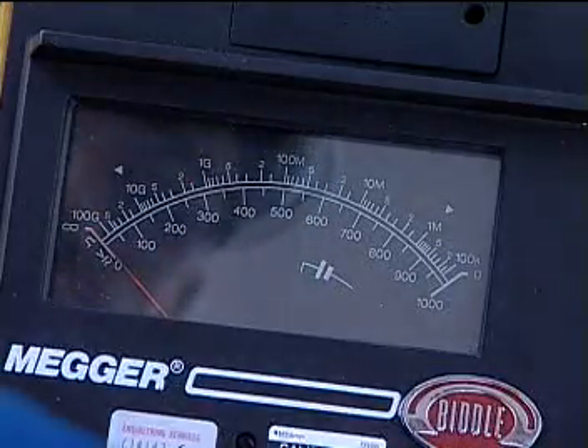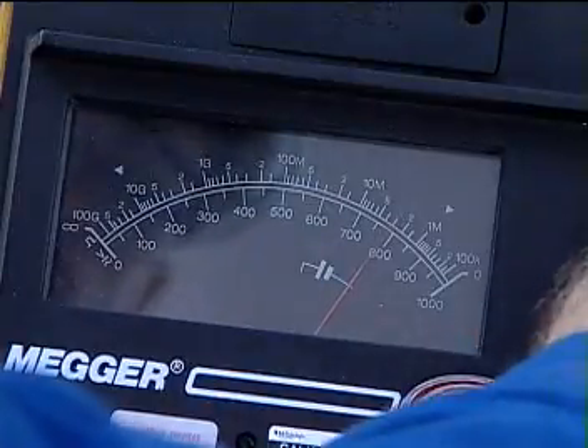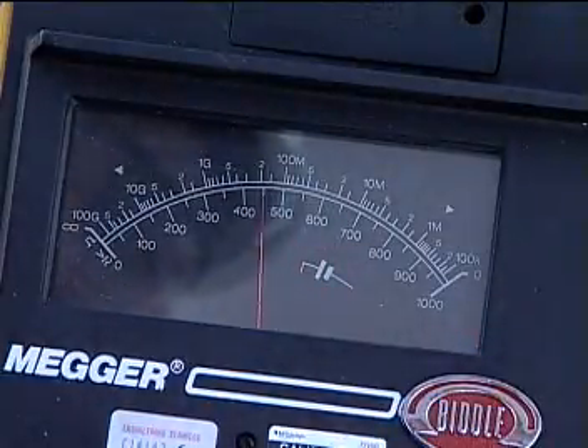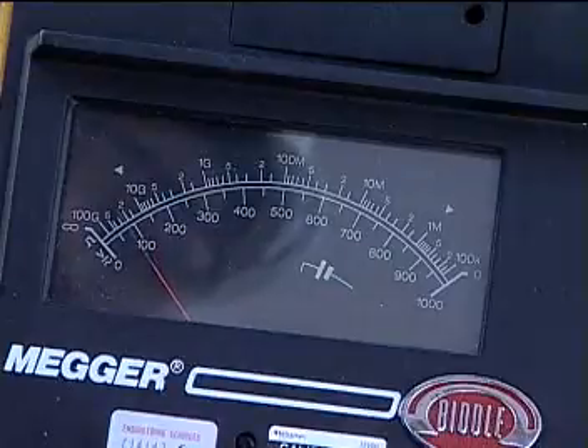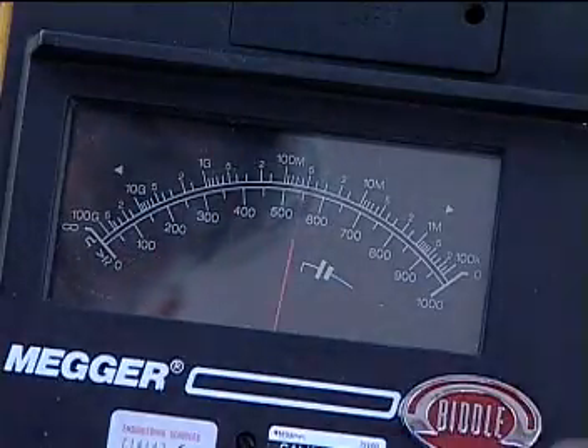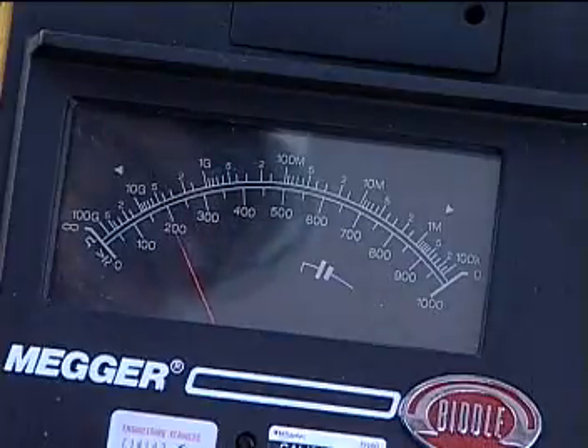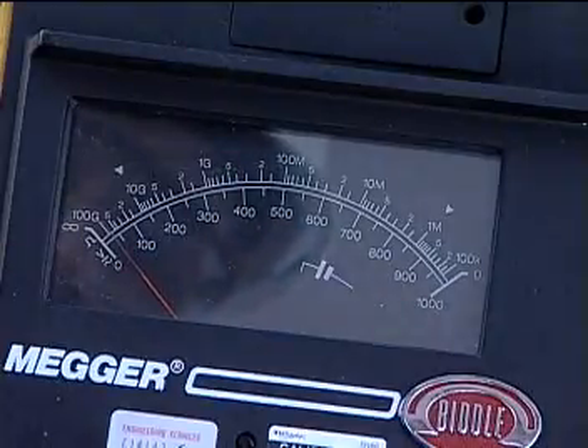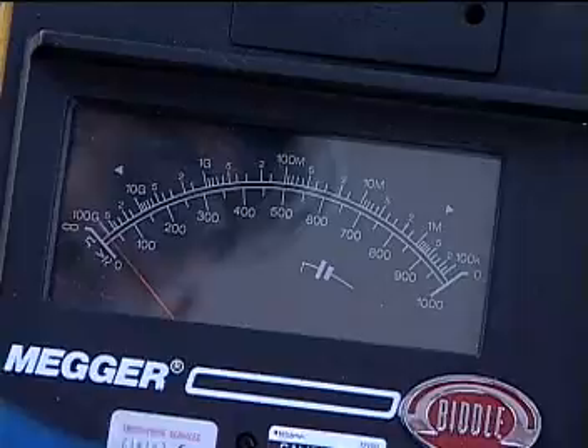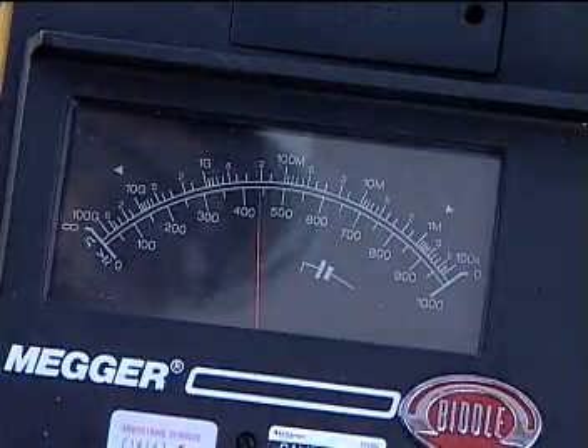A clean, dry, properly installed circuit should measure thousands of megohms, regardless of the heating cable length or measuring voltage. The readings should not vary more than 25% between the 3 voltages measured. If the variance is more than 25%, consult the troubleshooting guide in the Installation Maintenance and Repair Manual to resolve the problem.